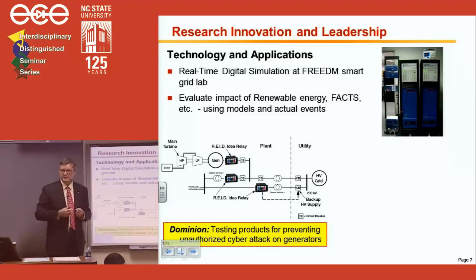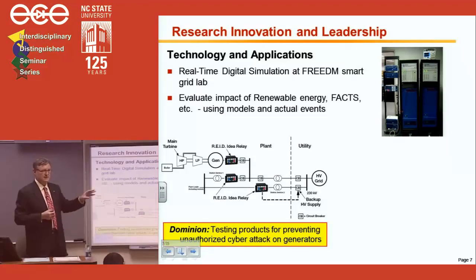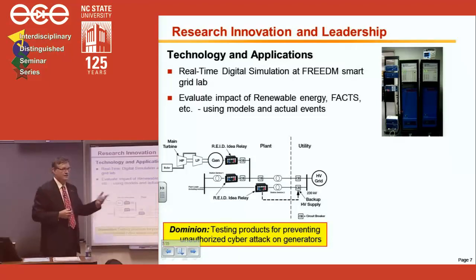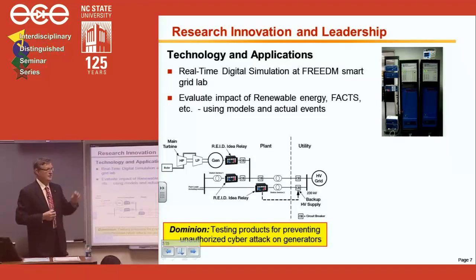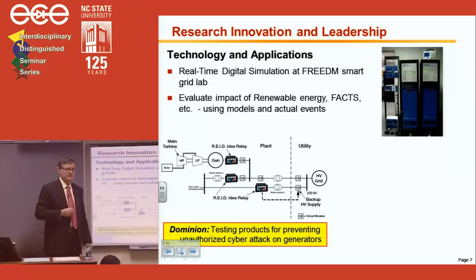Using our joint lab, we modeled those events with RTDS, and we were the first group in the industry to actually test what it really does. We found that if these devices aren't properly set and coordinated, they will trip and cause more harm than good. After this, NERC and FERC accepted some of the results and have been adjusting regulation based on the work done in our lab.